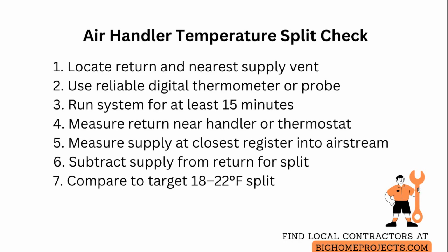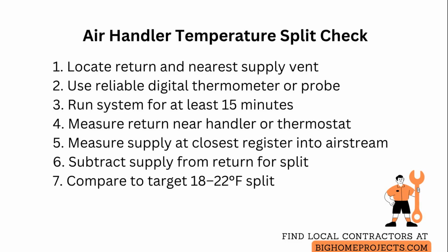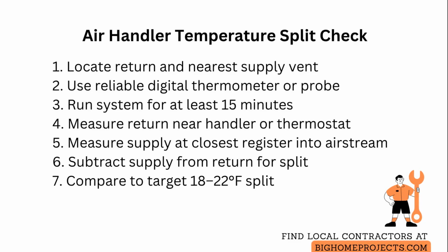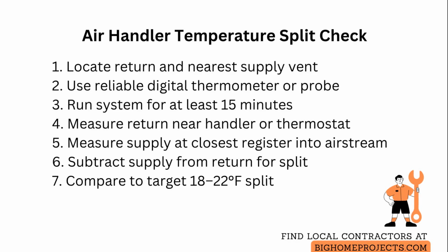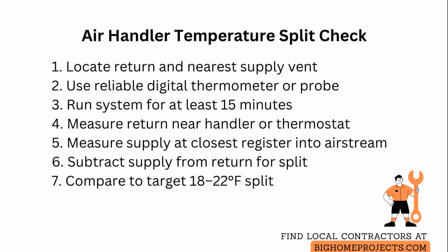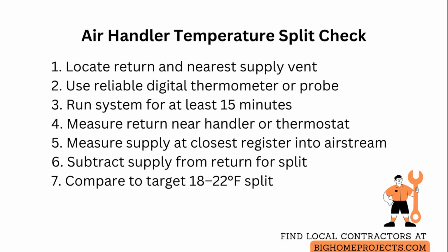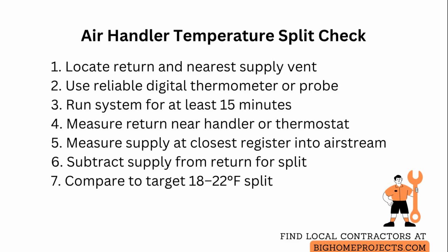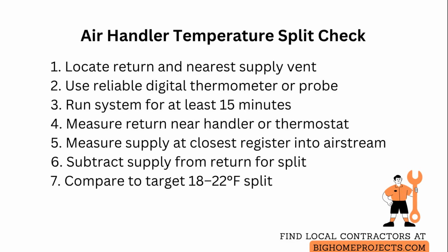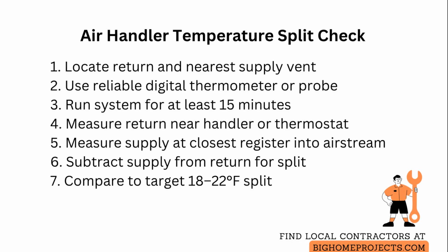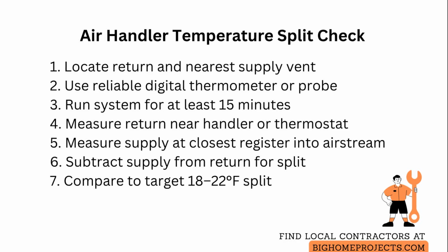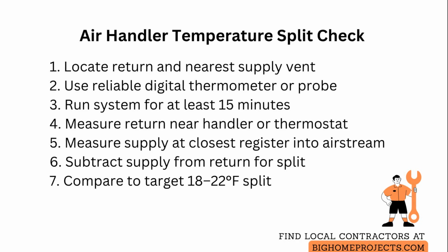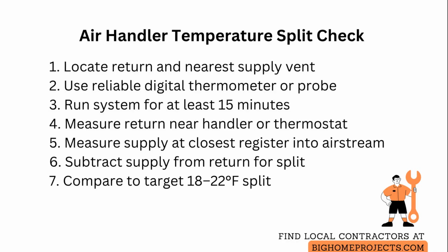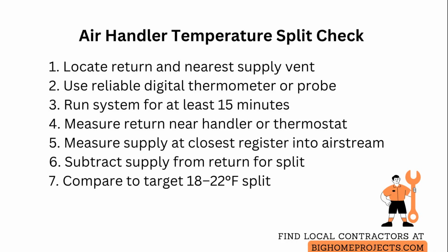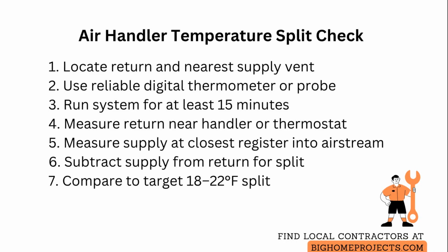Measure the return air temperature as close to the air handler return grill or the thermostat sensor as you can without blocking airflow. Measure the supply air temperature at the closest supply register to the air handler, holding the probe deep enough into the airstream but not touching the metal or plastic of the register. Subtract the supply temperature from the return temperature to get the temperature split and compare that to the expected target of 18 to 22 degrees Fahrenheit for properly functioning systems.